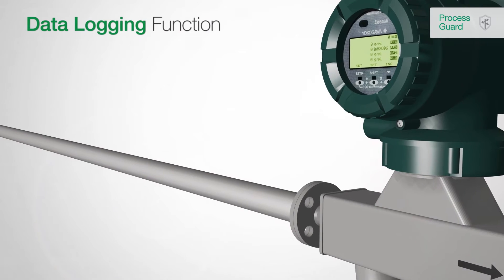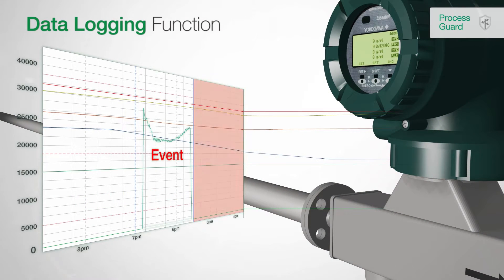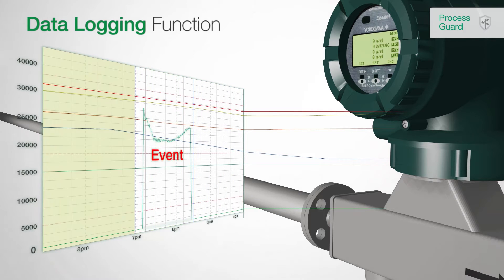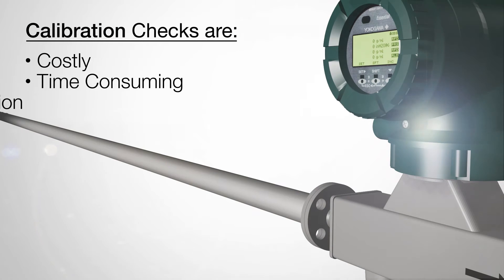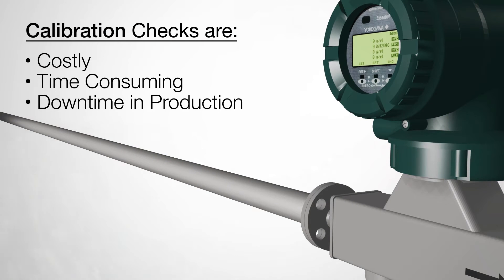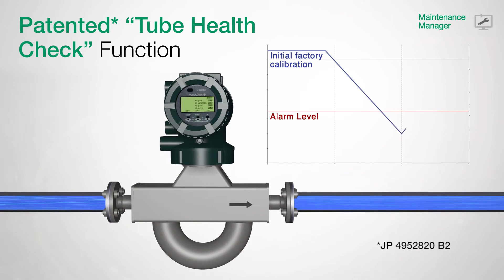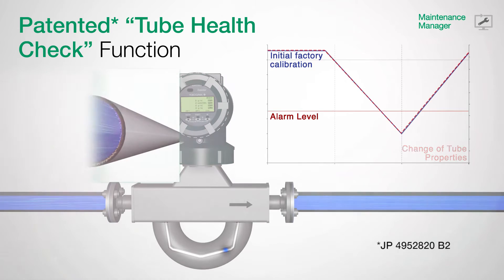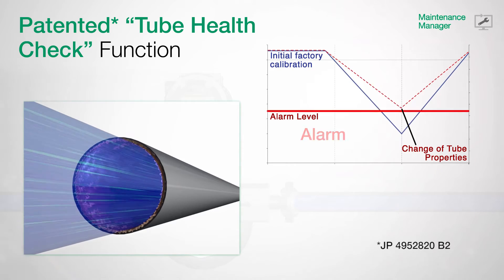The data logging function provides a total process analysis by showing the record of the measured data before, during, and after the event occurred. In regards to maintenance, calibration checks are costly, time-consuming, and cause downtime in production. But with the newly developed and patented Tube Health Check, a calibration check of an installed Rotomass can be performed while in operation without disturbing running measurements. Influences on the meter are diagnosed at an early stage, thus eliminating downtime and reducing your costs.